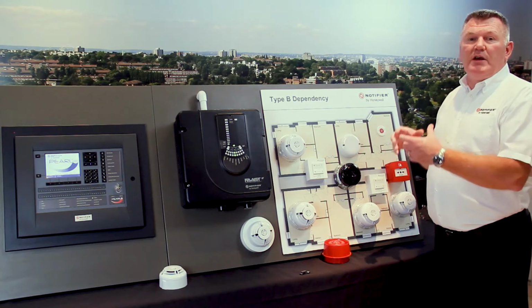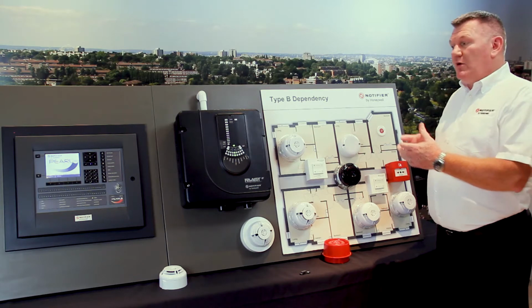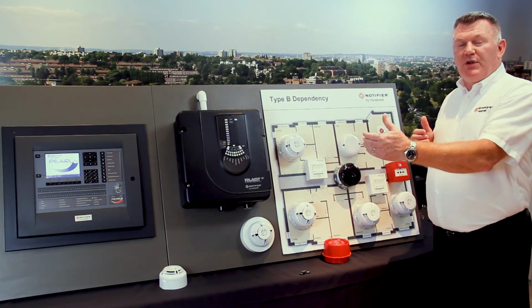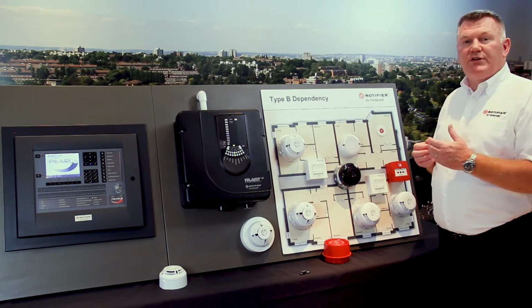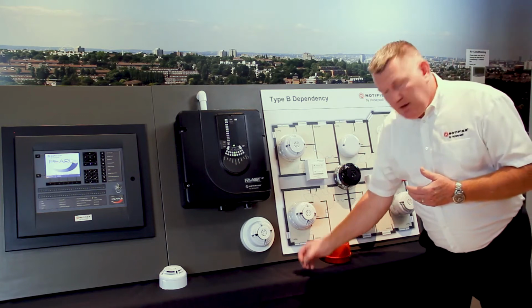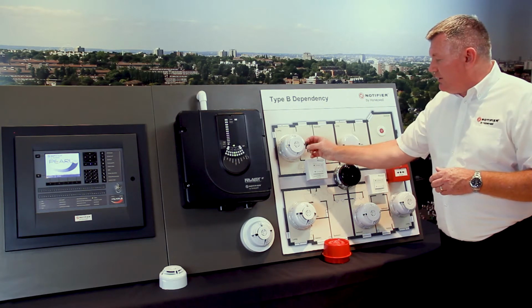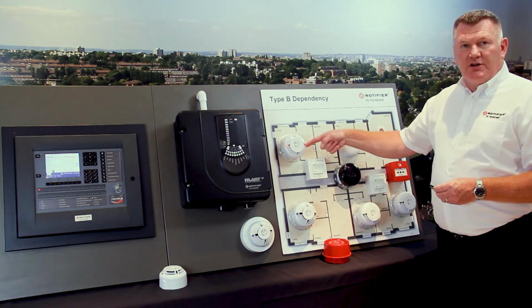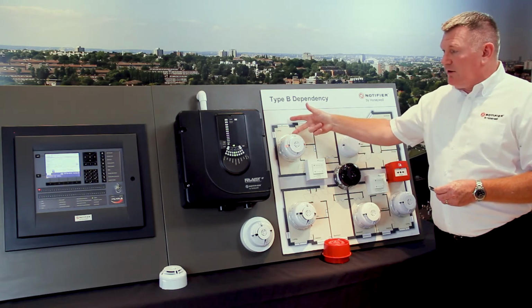We're going to allow the system to perform its full unconfirmed alarm, where it will run for up to 5 minutes. At the end of the 5-minute period, the system will do an automatic reset without anyone resetting the fire alarm control panel. I will use a test magnet because it's quicker. So I'll operate the smoke detector. This puts the detector into fire condition, sets the local sounder off with the flashing beacon on.